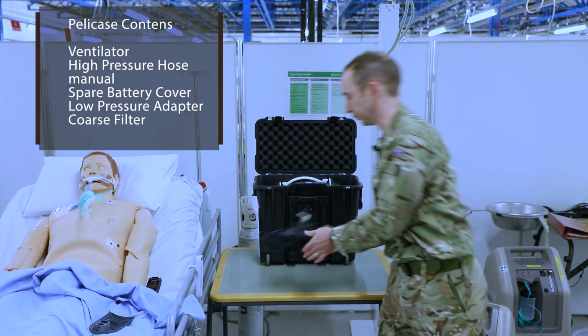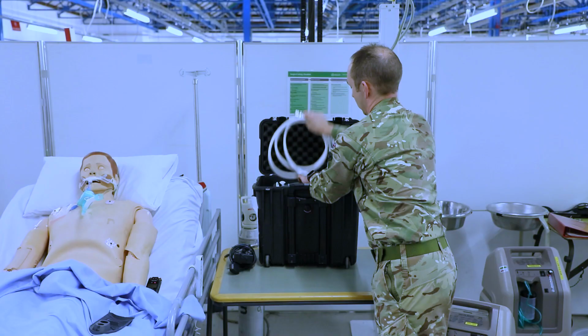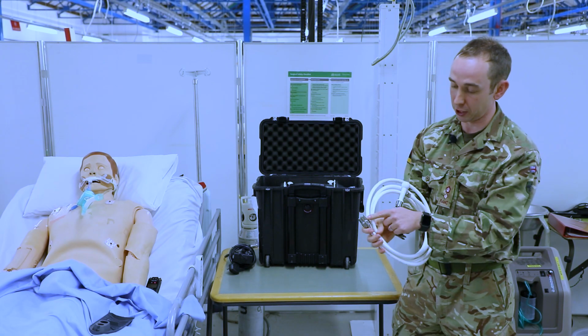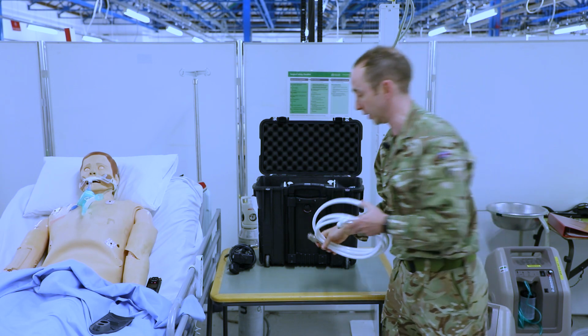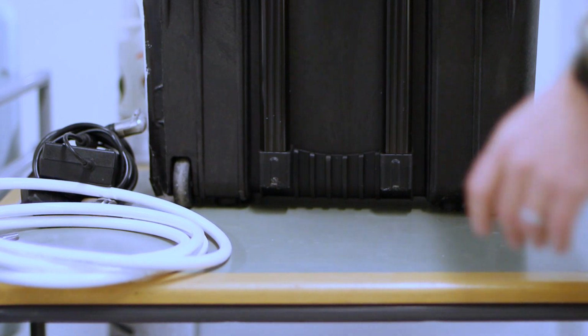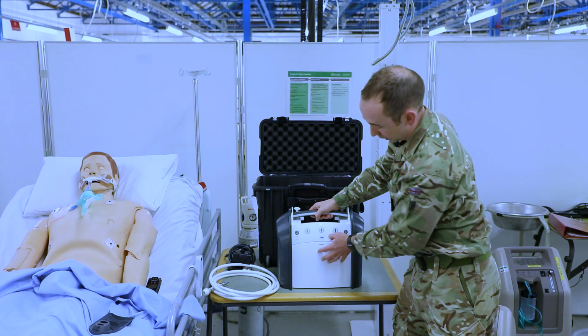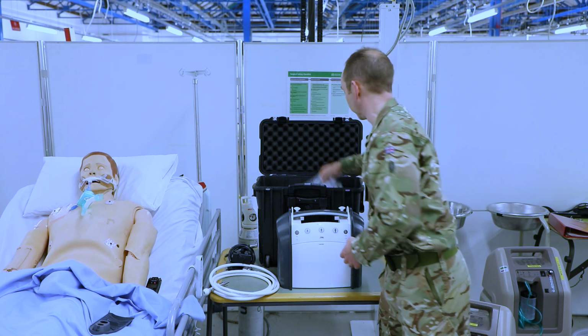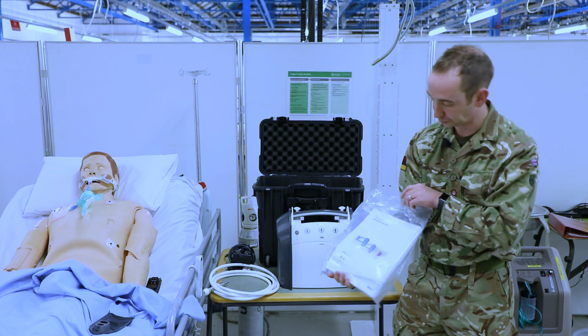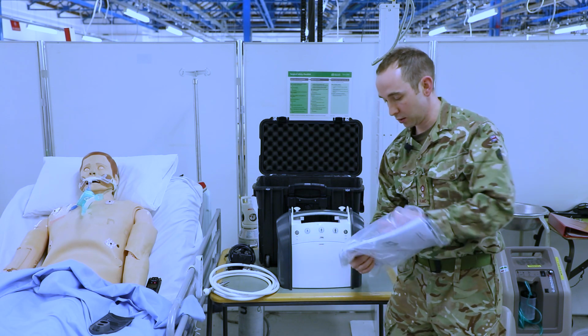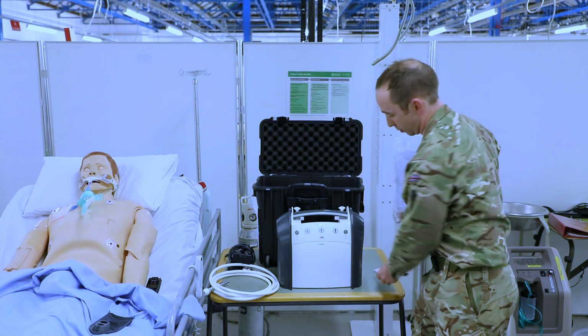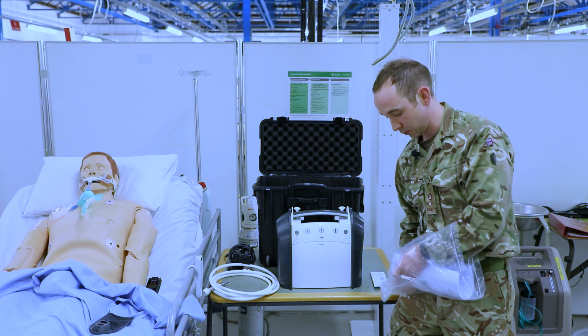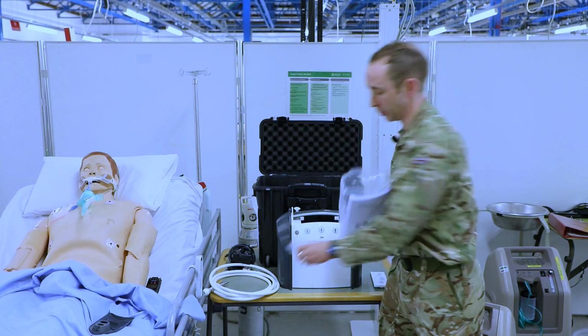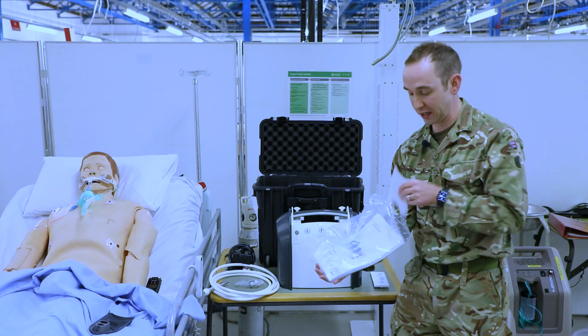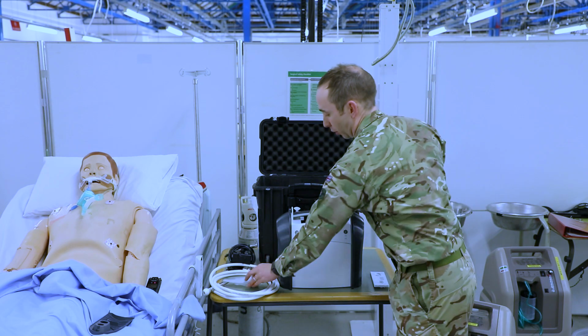When you open it up, what you're looking for is initially the power cable, the high pressure oxygen tubing, which has a non-interchangeable screw thread and a Schrader valve for attaching to our oxygen cylinders, the ventilator itself, and the ventilator should have a cover screen over the front of it. Then inside there'll be a manual. Added to that is a spare cover for the battery compartment at the back, a low pressure oxygen attachment, and lastly there will be a spare coarse filter which should come with every machine.